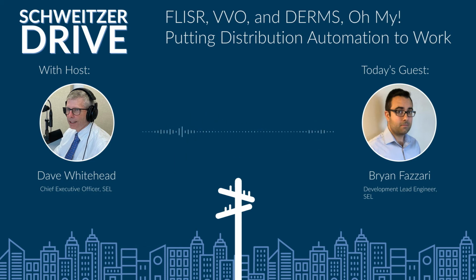When a utility is interested in something like that, they're looking at two different objectives: they want to make their distribution system more efficient, and they want to save money. The objective of volt-var optimization is twofold: reduce reactive power flow and decrease the voltage on the feeder. We'll look at those one at a time.